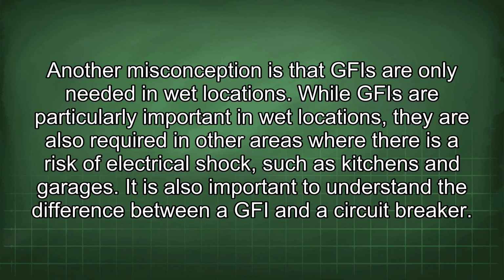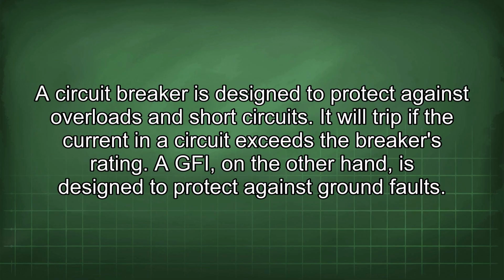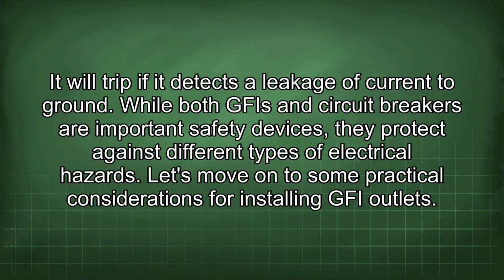It is also important to understand the difference between a GFI and a circuit breaker. A circuit breaker is designed to protect against overloads and short circuits. It will trip if the current in a circuit exceeds the breaker's rating. A GFI, on the other hand, is designed to protect against ground faults. It will trip if it detects a leakage of current to ground. While both GFI and circuit breakers are important safety devices, they protect against different types of electrical hazards.